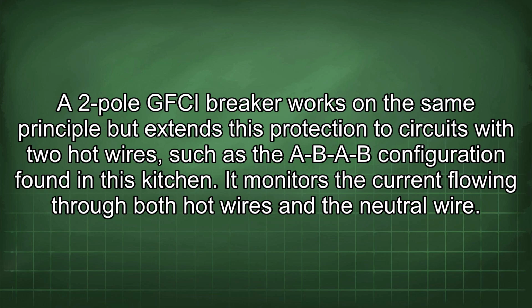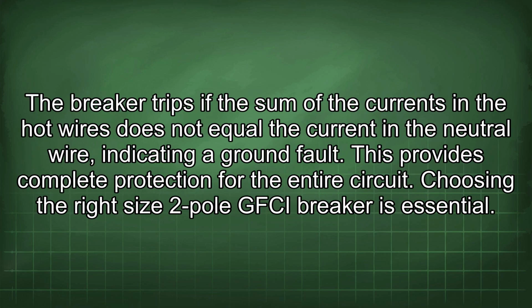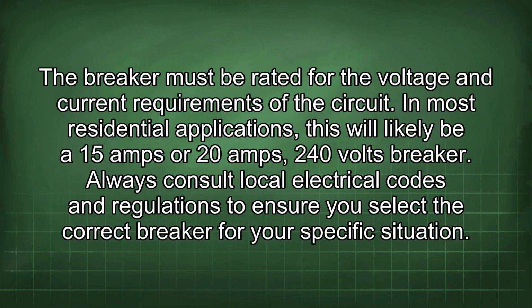It monitors the current flowing through both hot wires and the neutral wire. The breaker trips if the sum of the currents in the hot wires does not equal the current in the neutral wire, indicating a ground fault. This provides complete protection for the entire circuit. Choosing the right size two-pole GFCI breaker is essential. The breaker must be rated for the voltage and current requirements of the circuit. In most residential applications, this will likely be a 15 amps or 20 amps, 240 volts breaker. Always consult local electrical codes and regulations to ensure you select the correct breaker for your specific situation.